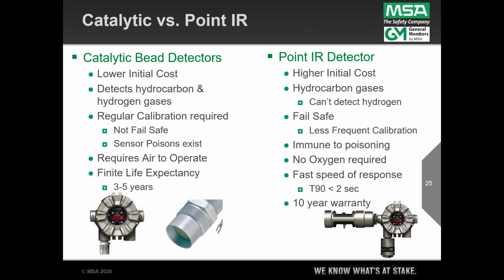So this is kind of a common sense. I just talked about most of this already. I won't spend a lot of time, but cat beads, here's a quick comparison head to head. They have a lower initial cost. So many customers say, hey, I like that, it doesn't cost me. That's true. But you're buying into regular calibration, because as I talked about, they're not fail-safe. Poisons exist. They have to be calibrated to check that they're available to detect and perform to the expectation. They require some air. In fact, they're not suitable for low oxygen conditions. It is a reaction that requires the principle of the heat combustion requires air for accuracy. And again, 3 to 5 years is pretty typical life expectancy on these guys, because they are a destructive measurement. It's like the light bulb is on, they're always energized.